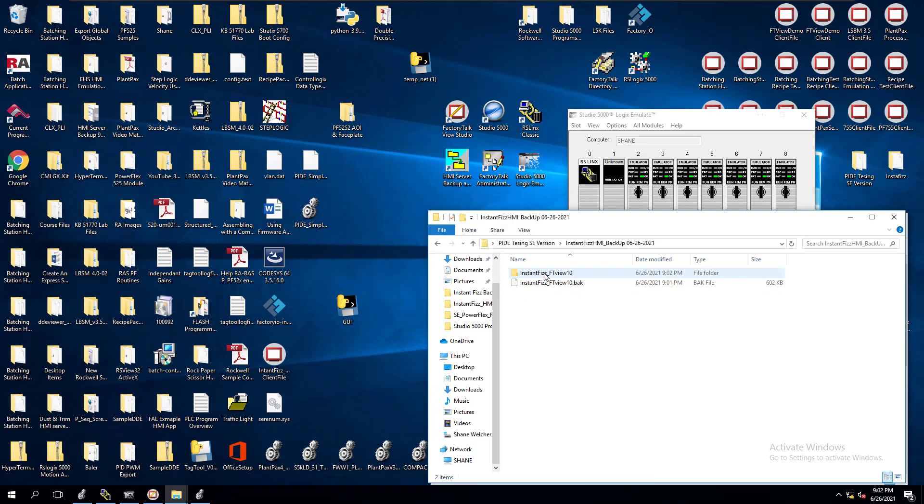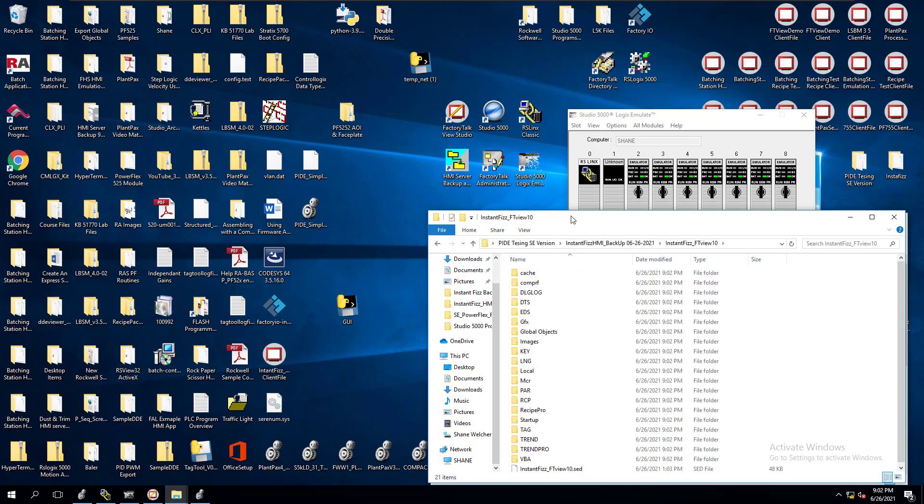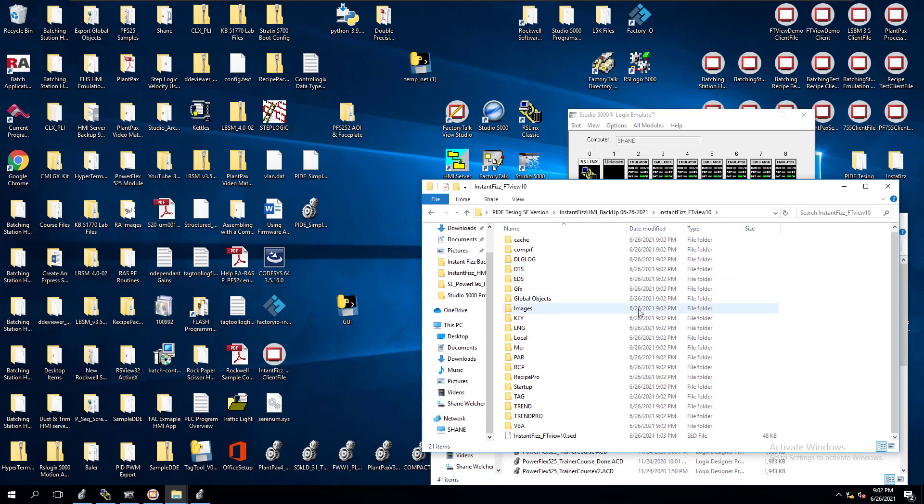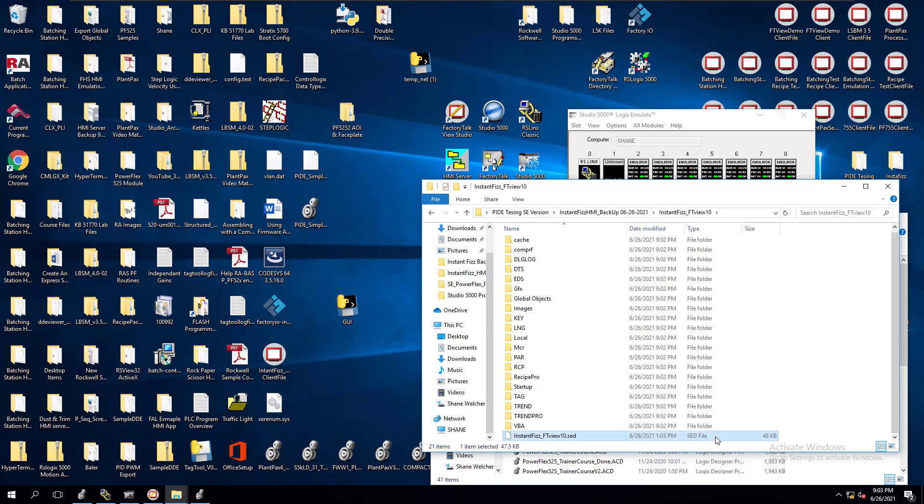With that said, now we can come in here and double check this. Now I will say there's one thing you need to look out for. There was an old tech note, I believe from Rockwell Tech Note, that said if it was like a weird number like 103 or 104 or something like that, that it could be corrupt. Now that does not mean that it is, it just means it could be. That was only on version like, I think it was FactoryTalk 6. But anyway, we're on FactoryTalk 10, so we shouldn't have that issue anymore. But just keep in mind these kilobytes right here, if that is 103, I believe the number was 103, it could be corrupt. Just make sure that you double check that it is.